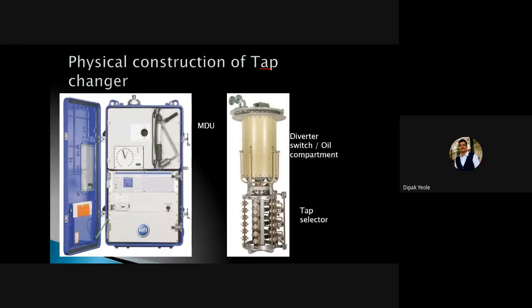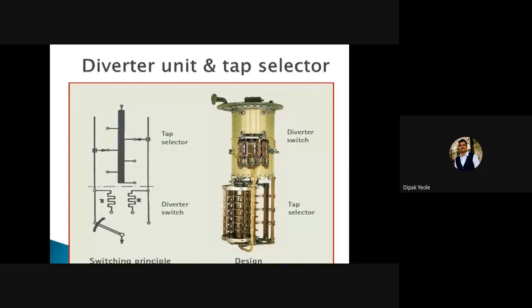This is the picture which we have seen last time, and this is the important switching principle of the on-load tap changer. It consists of two parts: the tap selector is available, and the arrow is available here, and we have to select according to our application. And this is called the diverter switch. This is the fixed part and this is the moving part, so this moving part will move in such a way that it will touch the current limiting resistors. This function which you have seen is the model or design of this particular on-load tap changer.